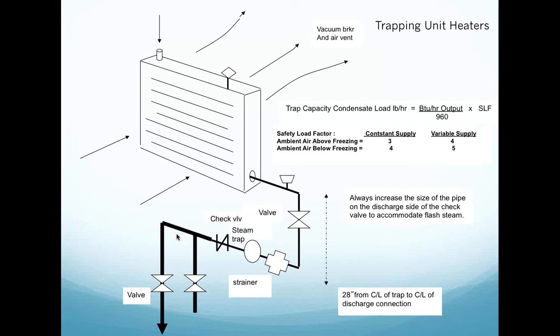And people ask me what that number is. The U.S. government, the military, pitches their steam and condensate systems 3/8 of an inch per 10 feet because they want to avoid water hammer. You may not need to go to that drastic step and pitch it 3/8 of an inch per 10 feet, but I want you to pitch it something. And the typical standard would be 1/4 of an inch per 10 feet. You have a discussion inside your facility, but I would like you to consider pitching your coils, your steam and condensate piping to make sure we use gravity to help us drain.